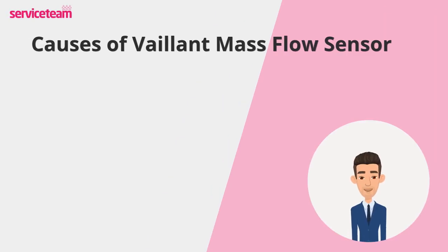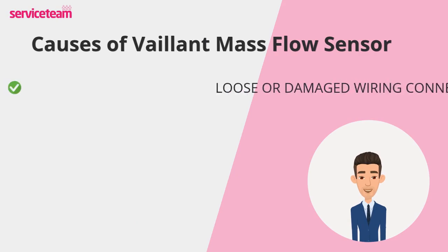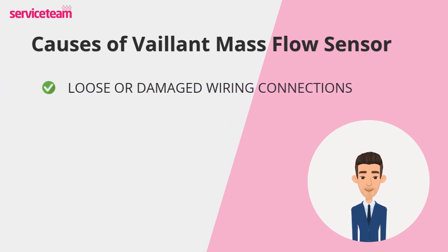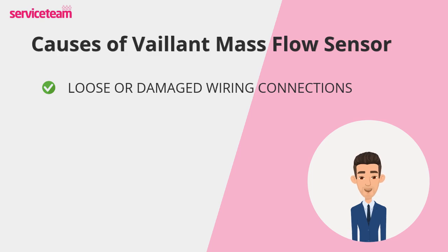Let's see what causes the Vaillant mass flow sensor error. The first cause is loose or damaged wiring connections. The mass flow sensor relies on precise electrical connections to communicate with the boiler's PCB. If plugs are loose, wires are damaged, or corrosion occurs, the sensor can fail to send the correct signals. This often triggers an F52 error code — a connection fault — causing the boiler to stop operating or behave erratically.